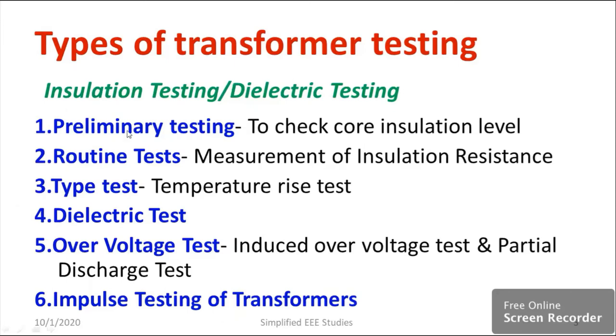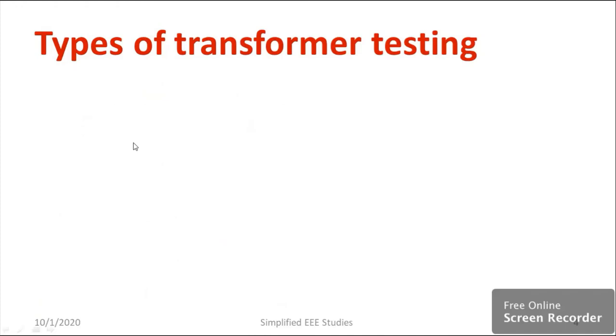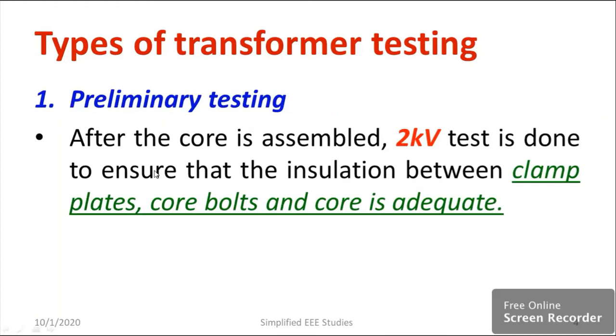Let me move on to preliminary testing. Once the core is assembled in the transformer, you need to apply 2 kV of test voltage. Why? You need to make sure that the insulation between clamp plates, core bolts, and the core part is adequate or not.